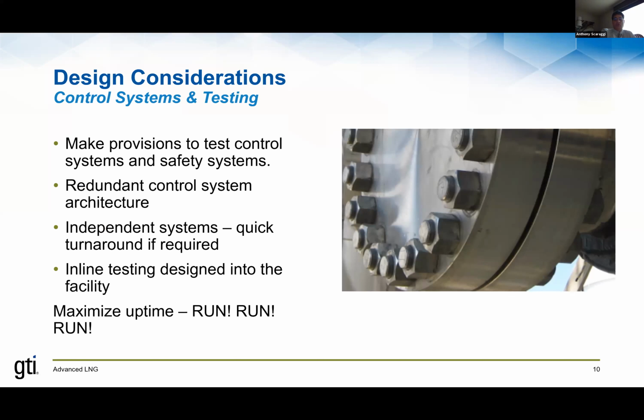Control systems that are in place in your facility need to be tested to be sure they're actually operating as they should. And you should build provisions into the facility to be able to test those control systems while the plant is online without affecting the safety or reliability of the operations. You can do that with redundant control systems, redundant control architecture. You can do that by having remote workstations that are used exclusively for testing purposes and that do not affect the actual operation of the facility. You can also do certain inline testing where you can take a component out of service while keeping the rest of the facility in service, and you maximize the uptime on that facility.